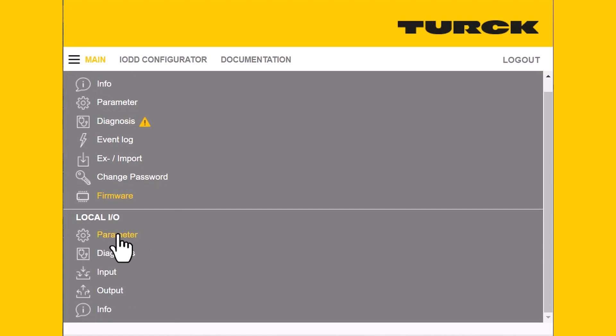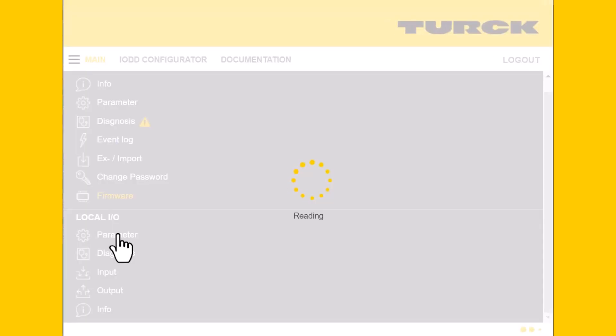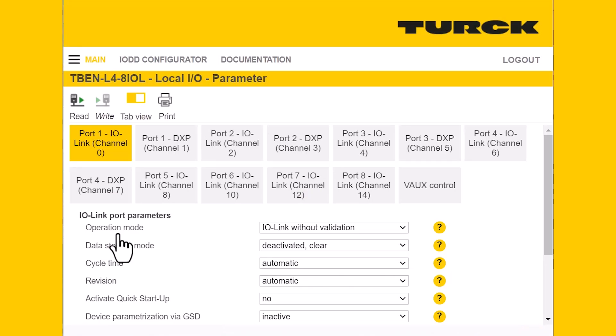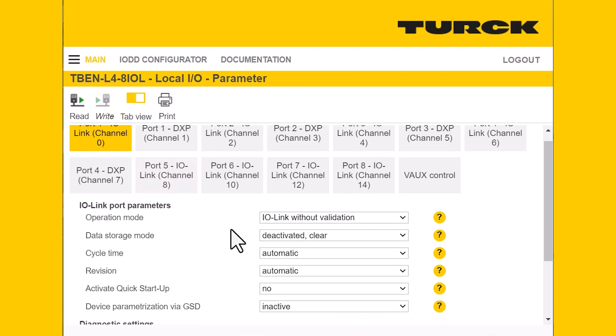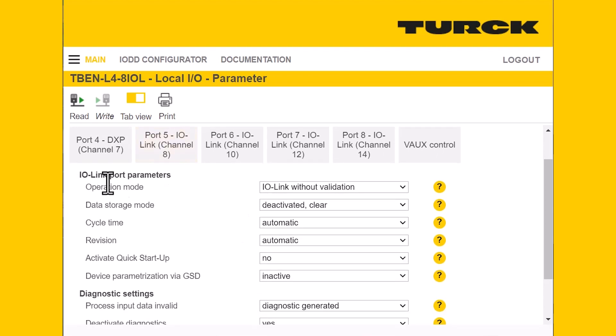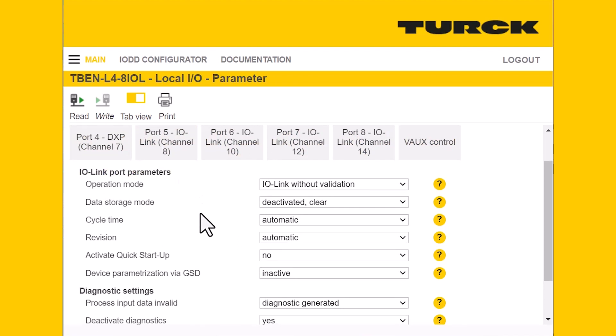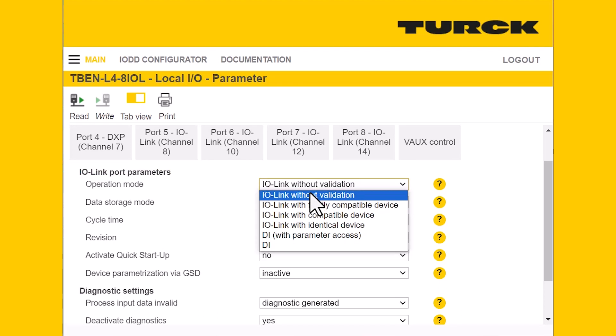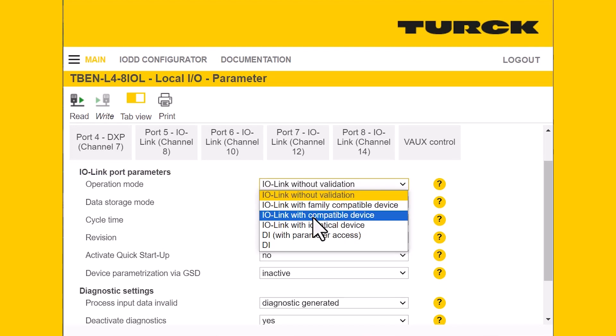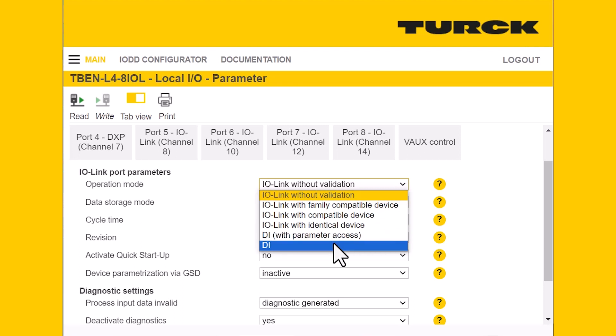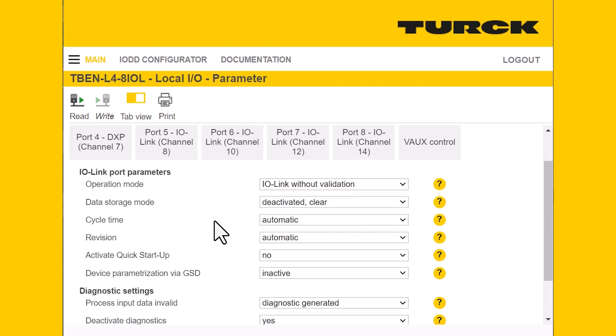Next, we'll go into our local IO section. This is where we actually parameterize the individual ports on the block. For port 1 on our IO-Link master, you can see at the top the different IO-Link port parameters — you can set the operation mode, whether you want it in IO-Link without validation, IO-Link with identical device, or simply as a standard digital input. You can also change your cycle time — I'd recommend leaving that as automatic.